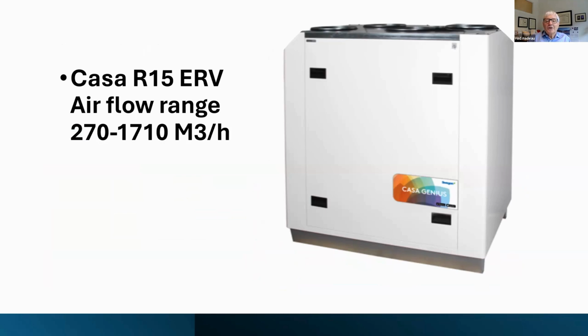So how can you use an ERV for all the heating and cooling? You simply do not have enough airflow capacity. Well, this is how integrated building design works. Lower the heat loss by 90% by building a better building envelope, which does not have to cost more, just make better choices. Now the design heat loss can be accommodated by the ventilation rate airflow if we double the minimum required ventilation rate. The benefit is a healthier home.